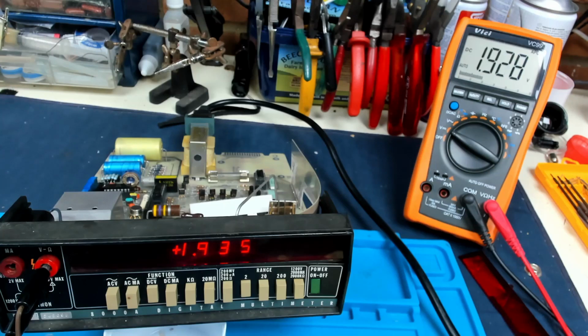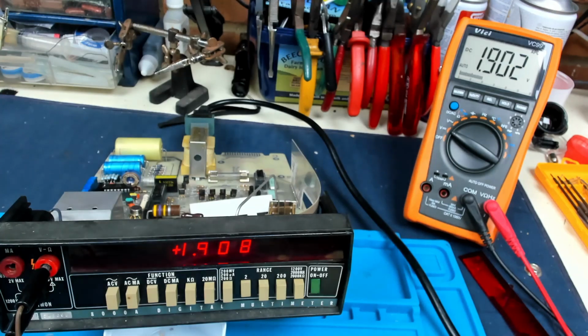All I can see is 1.9 on the bench power supply, it doesn't go any more detailed than that, but the meter shows it down to 3 decimal places. I keep dropping that down a little bit too far. Obviously in a calibration house they'd have digitally calibrated test power supplies, but that's going to be as close as I'm going to get. On the meter you can see it says 1.908.